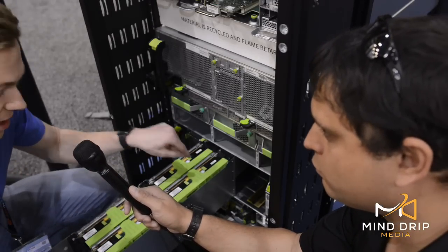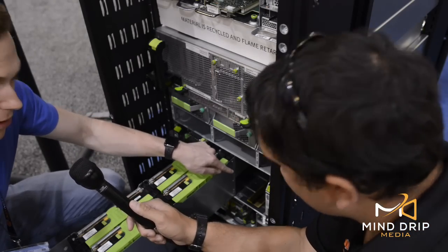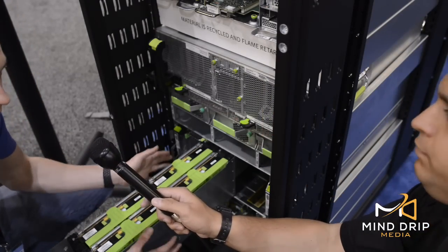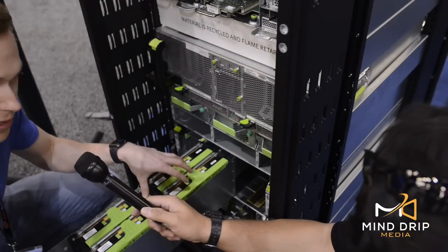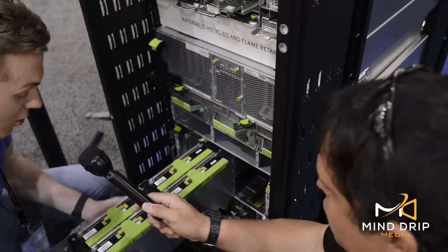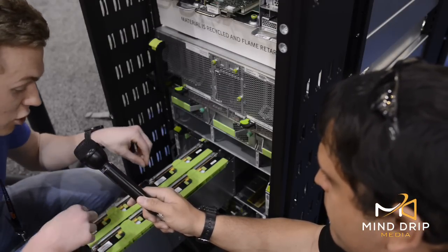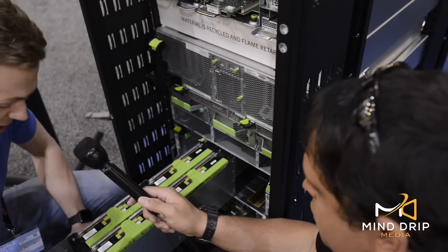And something to note in the rack here, you can see from the unit that was taken out, there's actually a power rail that runs all the way from the back to the front of the machine. All of that is solid state, so you don't have like an extra cable wiggling around, and that provides power to these machines even when the unit is pulled all the way out of the rack like this. So when we pull it out this way, it would still stay on, and you could pull an individual machine out and service it without taking the other ones offline or even disconnecting them from the network.